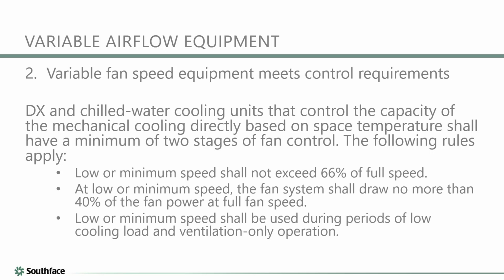Sure. The idea of variable speed equipment is that the fan motor can actually speed up or slow down to better match the load that's on the equipment. And as you can see in our bullet points, there are some limits that are set. It says if you have variable speed equipment, the low setting must not exceed 66% of the full fan speed. So there has to be a difference between the fan speed of your low setting and your high setting. And that magical number in this case is 66%.